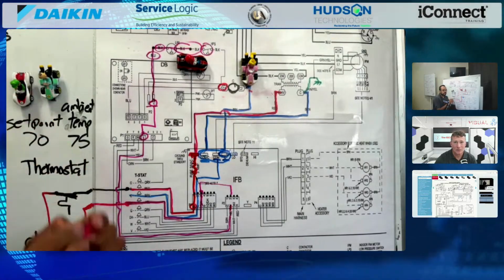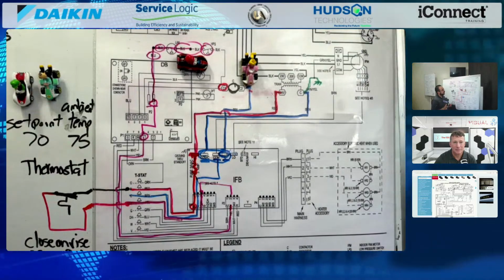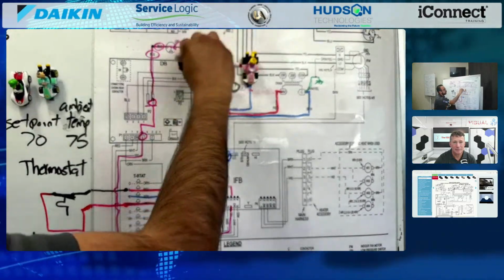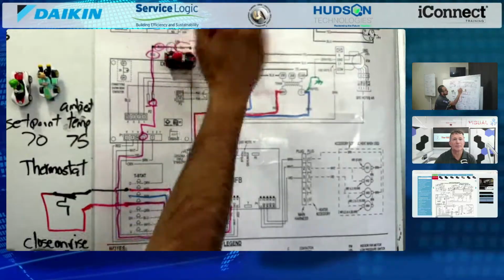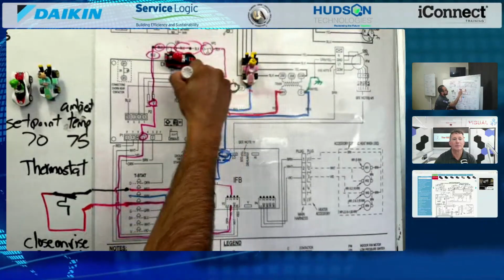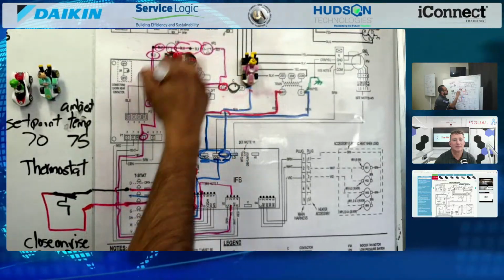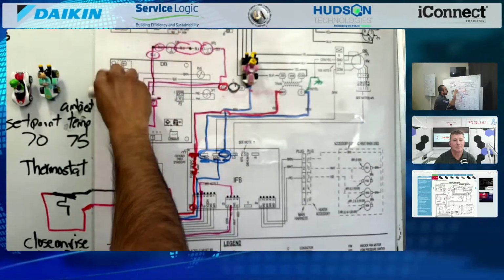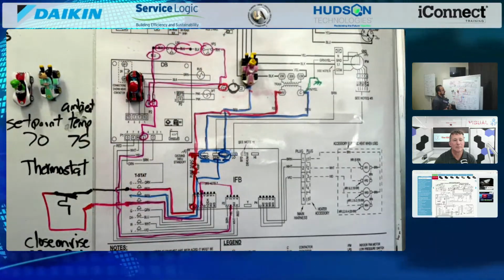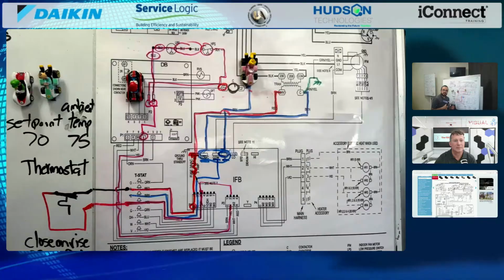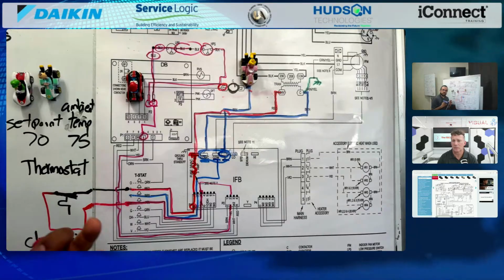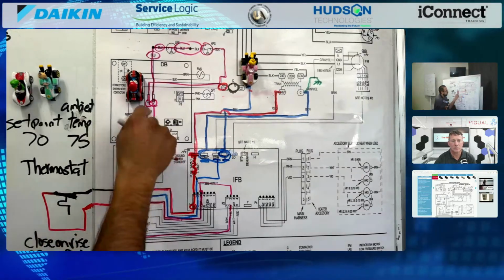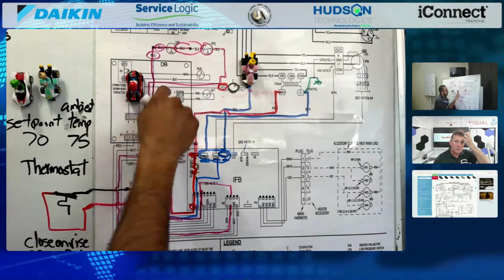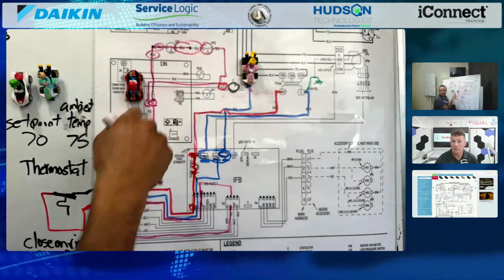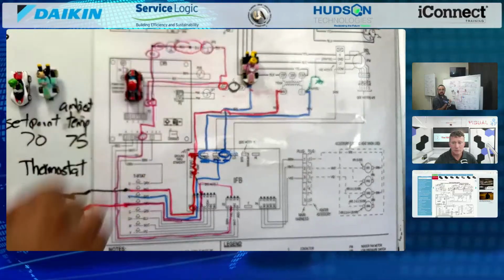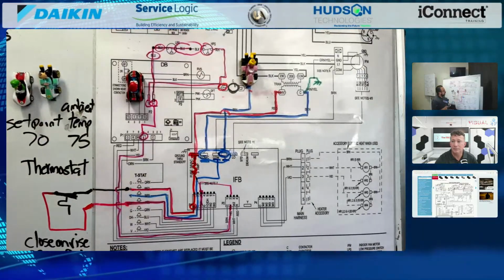Mario needs to go through, so here we go, there's no problem. Mario comes through and comes back as a black wire to T1. So boom, Mario makes it all the way over to T1. I always tell the guys, as a pro tip, with power off you can disconnect Y1 and T1, and if you check continuity and have a path, your safeties are closed. Mario's going to be able to go through. Your track is good, your track is through.